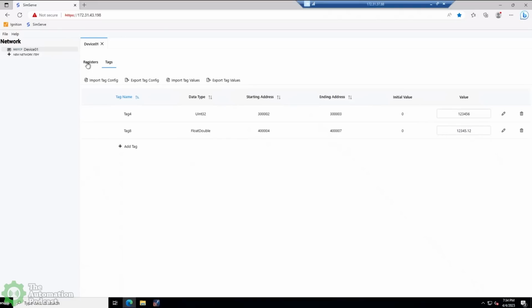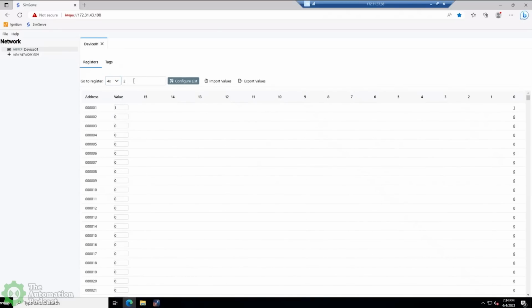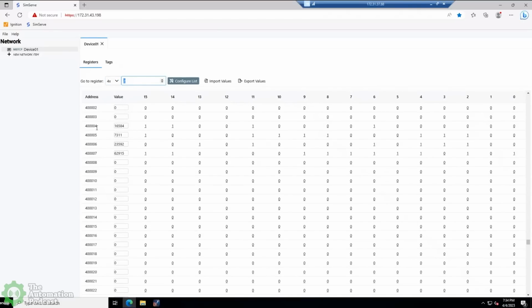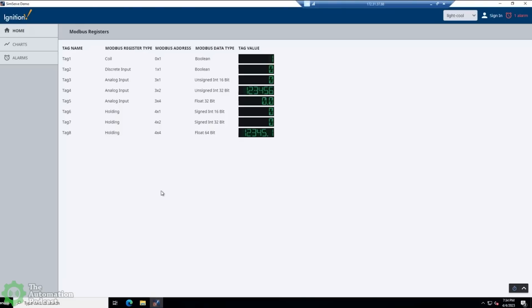Okay. Let's flip back over to the registers and see what SimServe did. All right. 4x4 down to 4x7. This is what SimServe calculated needed to be in each register. And then if we flip over to the Ignition perspective, HMI, we get that same number we put in, 12345.1. And it looks like I've got the precision turned down to 1 decimal, so we just see the 0.1 instead of the 0.12. But as you can see, it's working. And that's huge, because if you had to do that manually, like figure out what those numbers were, it could really give you a headache, right? And so a lot of us would turn to Excel and play around in there. But having that built in, being able to create tags and do that, that's such a time saver.